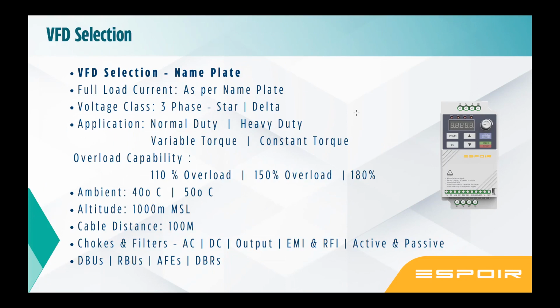If it is 22 amps, now at 45 degree, you reduce 5% of 22 amps, means roughly it will deliver 20 amps. In a smaller size, it is okay, it's manageable. But if your drive size becomes bigger, say 200 amps, 300 amps, this percentage of current becomes very important. Now, what is the solution? How do you derate? If you derate by 5%, 10%, it becomes 7.5 kilowatt. So now, to run an 11 kilowatt application at 50 degree, your drive has become a 7.5.